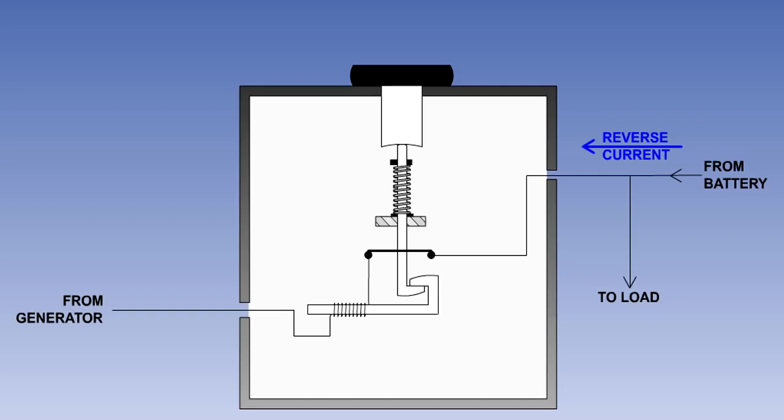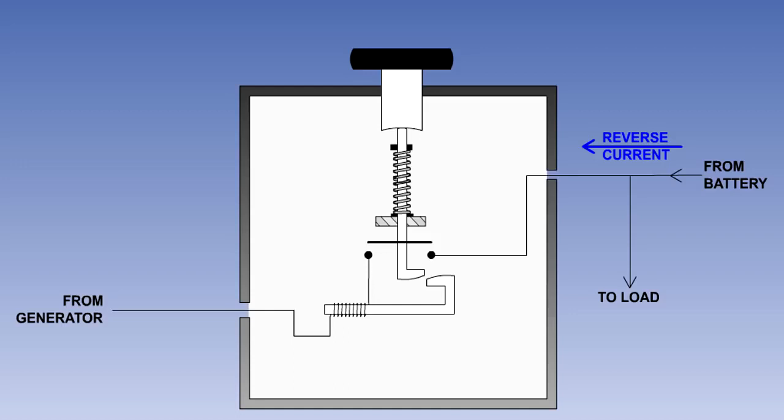However, when the current flow through the coil is reversed, its magnetic field operates in the opposite direction. At a preset current level, this field will have sufficient force to break the latch and open the contacts.